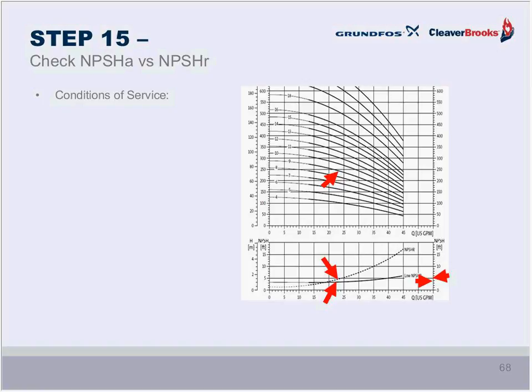Next, we have to take a look at the net positive suction head. Our flow, remember, is at 23 gallons a minute, which I've indicated by these red arrows. In the conventional impeller design, which is that dashed line down at the bottom, we need to figure out what our net positive suction head required is by the pump, and then we have to add 2 to 4 feet to that. And we're coming in at, what is it, about 5 feet. So if we added 2 feet to that, that would give us 7, and that would be less than the 8 feet available. So that would be okay, but we always should be conservative. You could get yourself into trouble, so we should add the full 4 feet of safety allowance, which means you'd have something like 9 feet required. And that's a red flag.